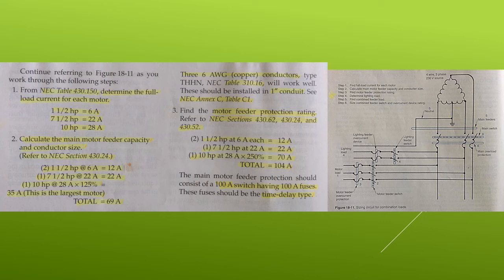Step 2, calculate the main motor feeder capacity and conductor size. For this, refer to NEC section 430.24. For the two 1.5 horsepower motors at 6 amps, we have 12 amps. For the 7.5 horsepower at 22 amps, we have 22 amps. And for the 10 horsepower at 28 amps times 125%, we have 35 amps. This is the largest motor. So we have a total of 69 amps. So three 6 AWG copper conductors, type THHN, again from NEC table 310.16, will work well. These should be installed with 1-inch conduit. See NEC Annex C, table C1 for that.